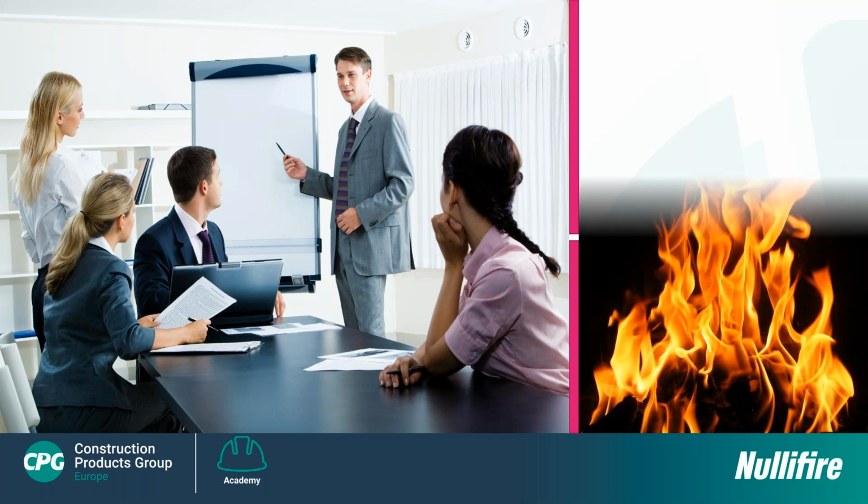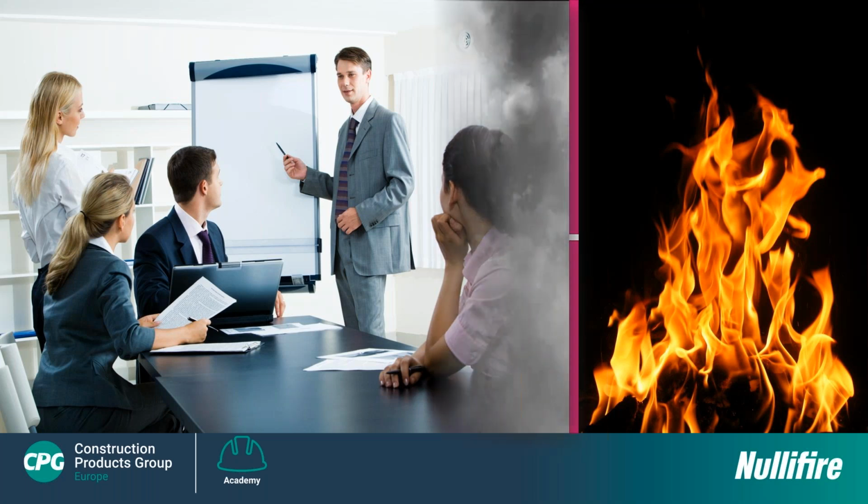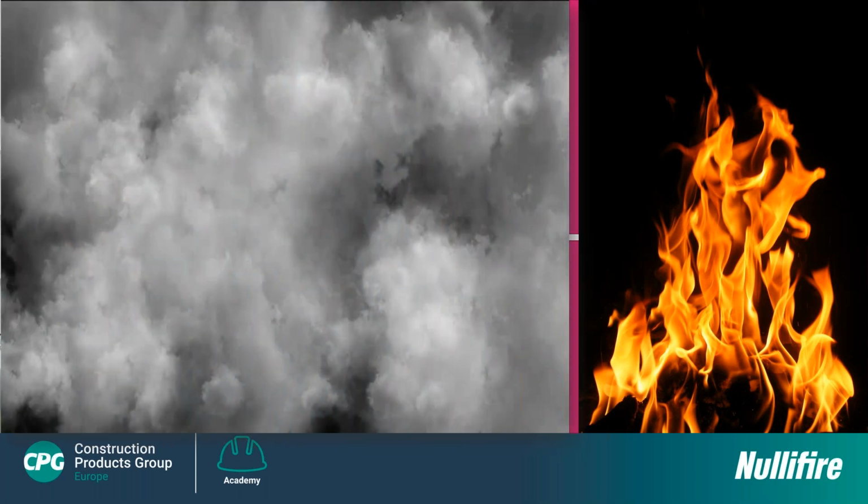So if there's a fire in the room next door, how long would it take for smoke through that hole to fill that room? I normally ask, when we do a Teams call, for people to tell me what they think it is, but because it's Ramadan, you can't tell me. It's basically 3 minutes and 20 seconds, based on the speed that smoke travels with the pressure created from that fire. This highlights the importance of compartmentation, and how a small opening could cause major problems. It's not just the big voids where we're putting fire batts through. You've got to look at the small openings as well.